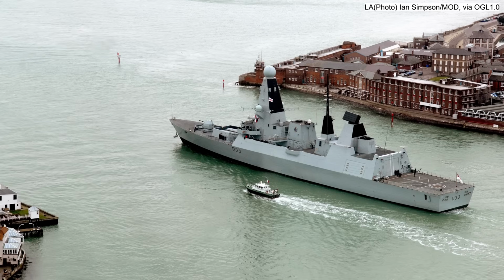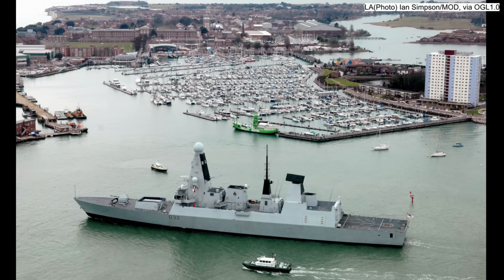This is the intercooler recuperator system designed by Northrop Grumman. This intercooler unit reportedly had a major design flaw that causes the gas turbines to overheat and shut down under high ambient temperatures. Without the gas turbines to supply part of the electricity needed for the ship's integrated electric propulsion, or for the hotel load, the remaining diesel generators on the ship are not enough to handle the electrical load on their own. When this happens, the diesel generators shut down as well, presumably due to the triggering of safety thresholds, leaving the ship with no sources of power.